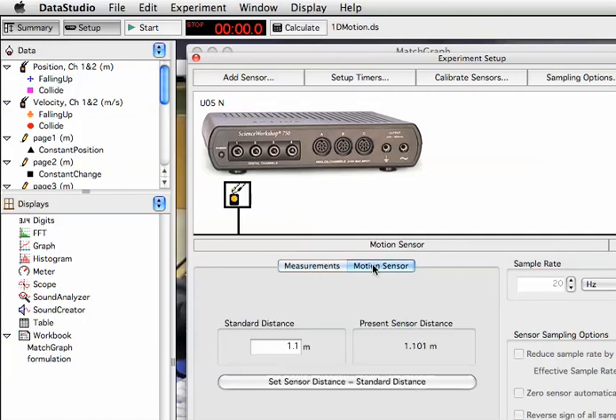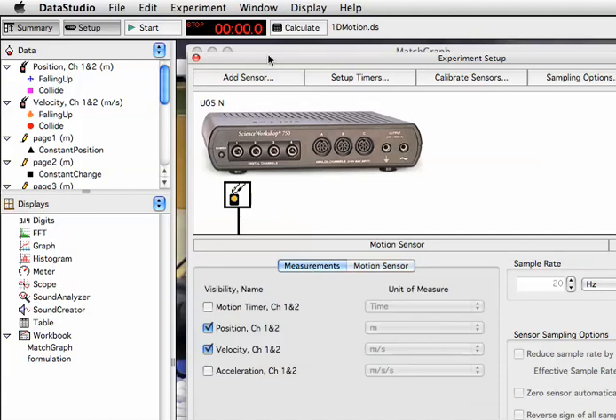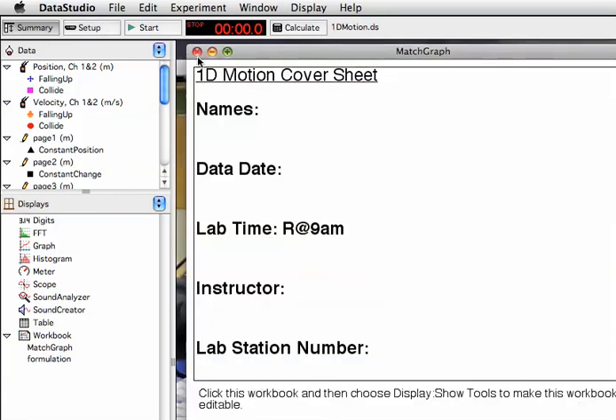To check your calibration, you can just go back to here, and I can move this block closer or further away and just see if it's reading the correct present sensor distance. But do not click this button unless you've carefully measured out a standard distance first. So again, I'm going to get out of calibration by clicking measurements, and then I can close the setup window.